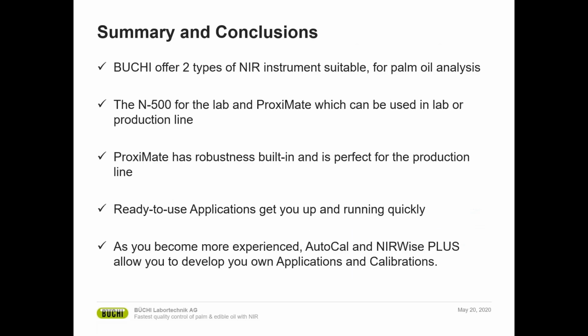So really, just to summarize what I've tried to cover is, we offer 2 types of NIR instruments that are suitable for the palm oil industry. The N-500 is for top of the line, high performance NIR, which is usually more suited to the laboratory environment. And you may find that if you develop applications and calibrations on that instrument, it's possible to port those out to ProxiMates that are based perhaps closer to the production line, where you can maximize the value you can get from those NIR instrument measurements.